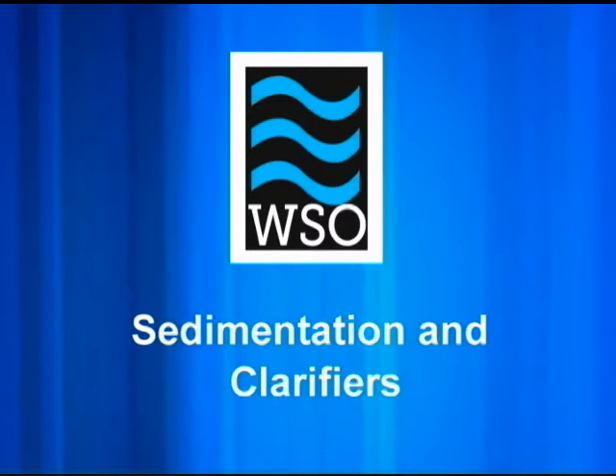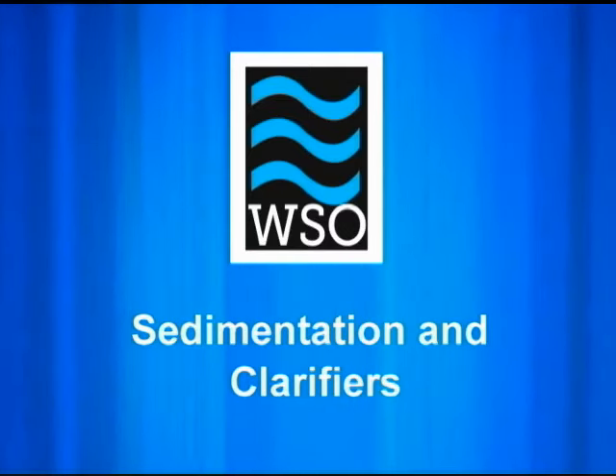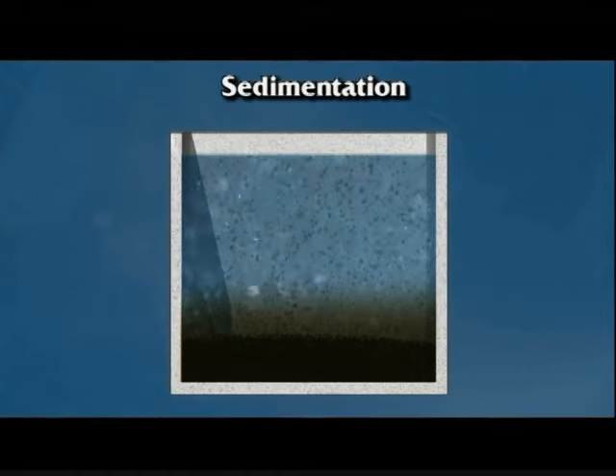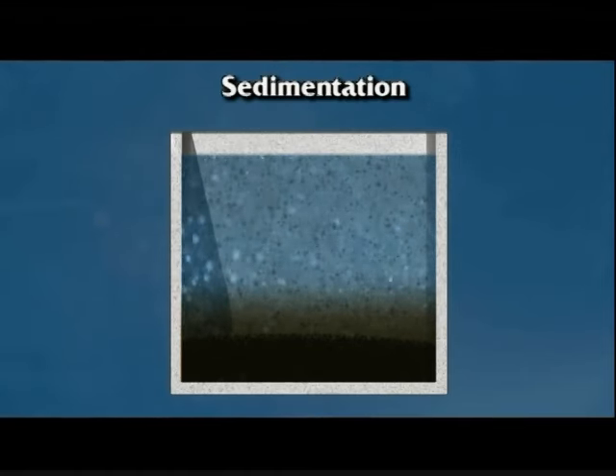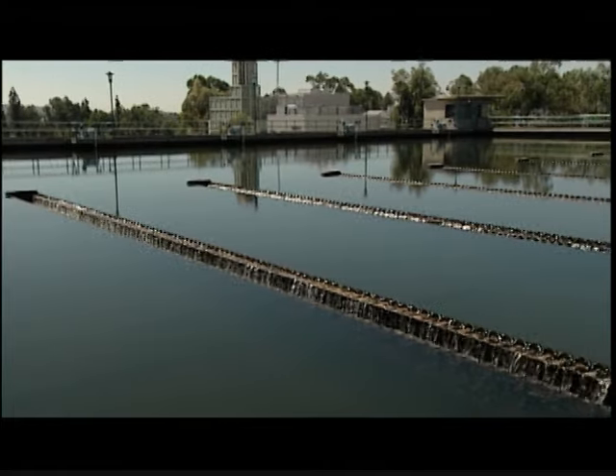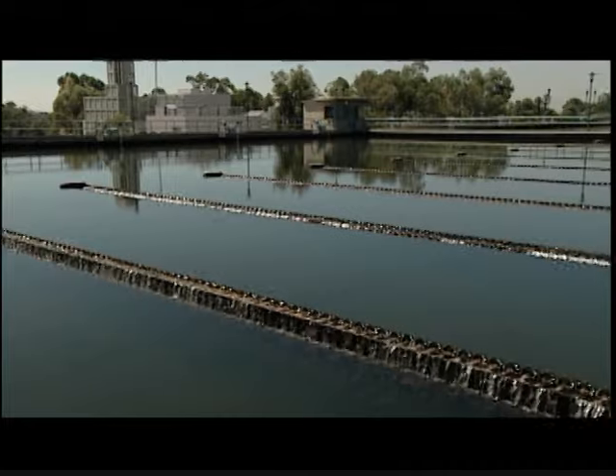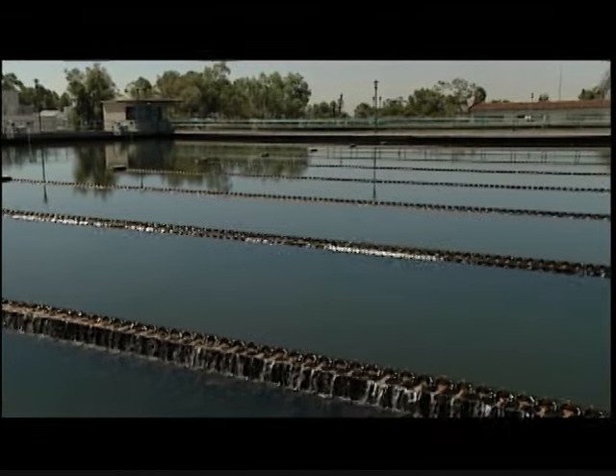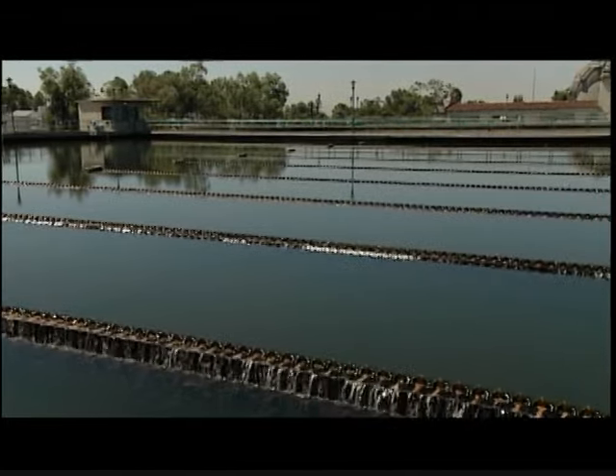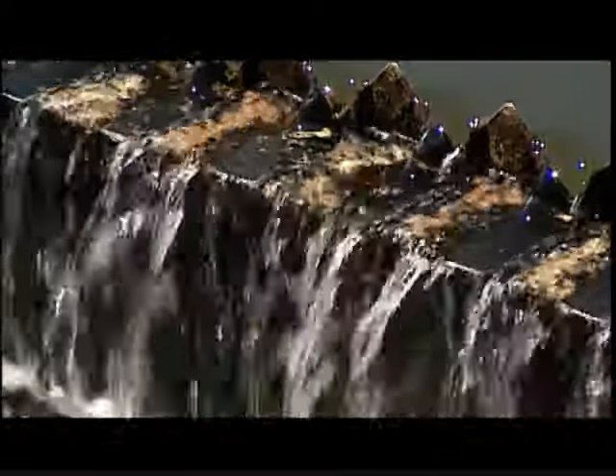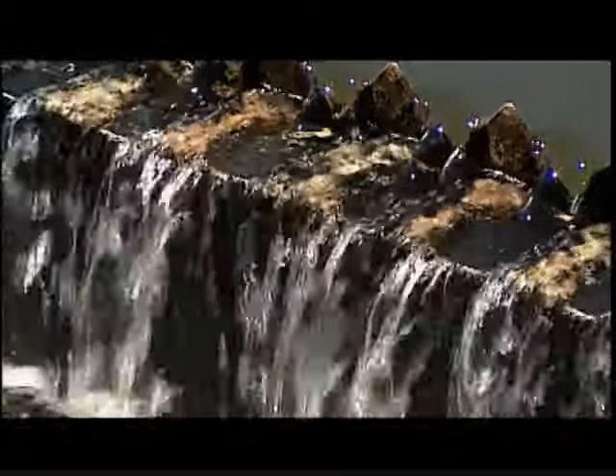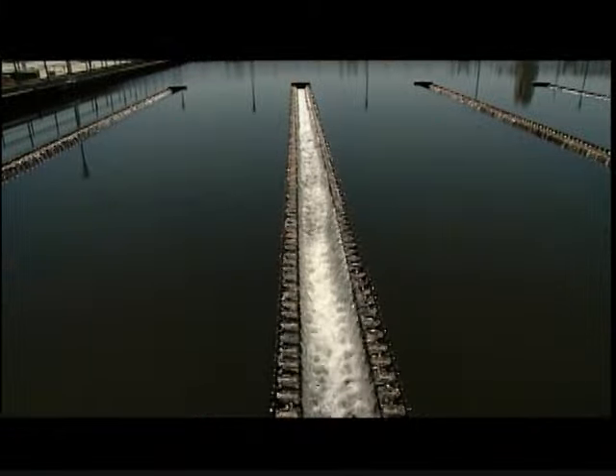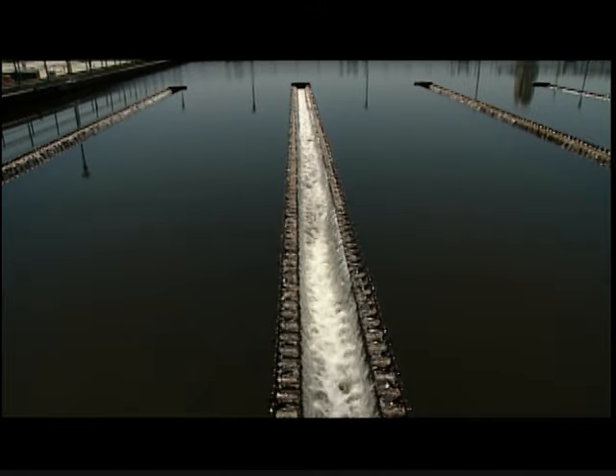Once proper floc has formed, it must be separated from the water through sedimentation or clarification. This process takes place in a rectangular, square, or round tank called a sedimentation basin or clarifier. It should be noted that direct filtration plants do not include a sedimentation or clarification unit process.